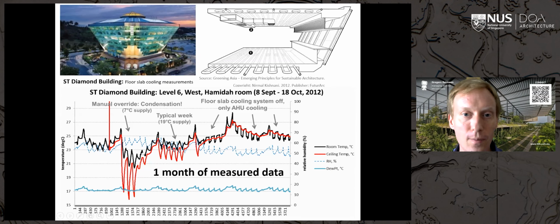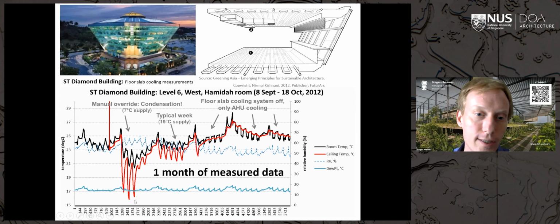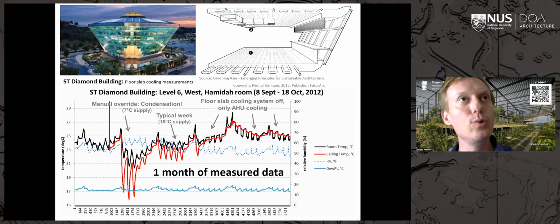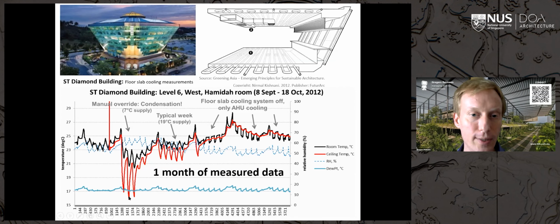And then we have the week before that, where they switched over the system to manual operation. So instead of feeding 18-degree water into the slab, they took the normal chilled water at 7 degrees and put that into the slab. And that's why you can see that the ceiling temperature dropped a lot during that week. And critically, it crossed the dew point. This is the dew point inside the office. So once you have something that's cooler than the dew point, then dew starts forming, just like when you take a water bottle out of the fridge, immediately you will have dew forming. So during these 3 days where we dipped below, there were water droplets collecting on the ceiling, and there was, you could say, rain indoors. And that's why they quickly put it back to automatic operation.